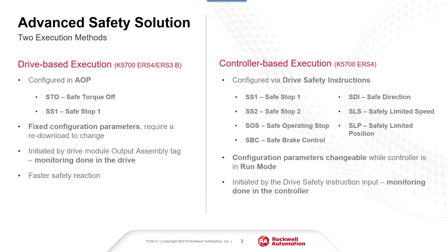Now let's take a look at the two execution methods for an advanced safety motion solution. First is drive-based execution. The parameters for the safety functions are configured in the drive module add-on profile. The available safety functions include Safe Torque Off and Safe Stop 1. Once configured and downloaded to the controller, the parameters for the safety function are fixed. Any changes would need to be done offline and then re-downloaded to the controller.